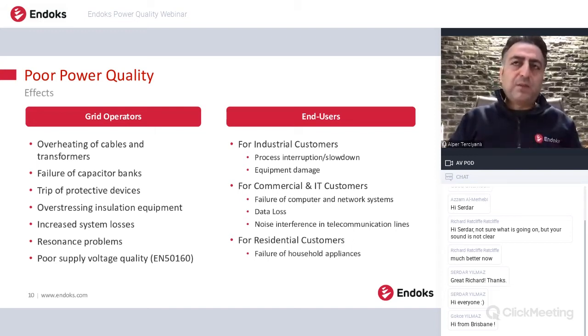All these protection devices may not measure voltage as they should because of nodes and the harmonics, and this mismeasuring causes malfunctioning of the protection devices. And of course, the harmonics create overstressing on the insulation equipment, and also overvoltage.